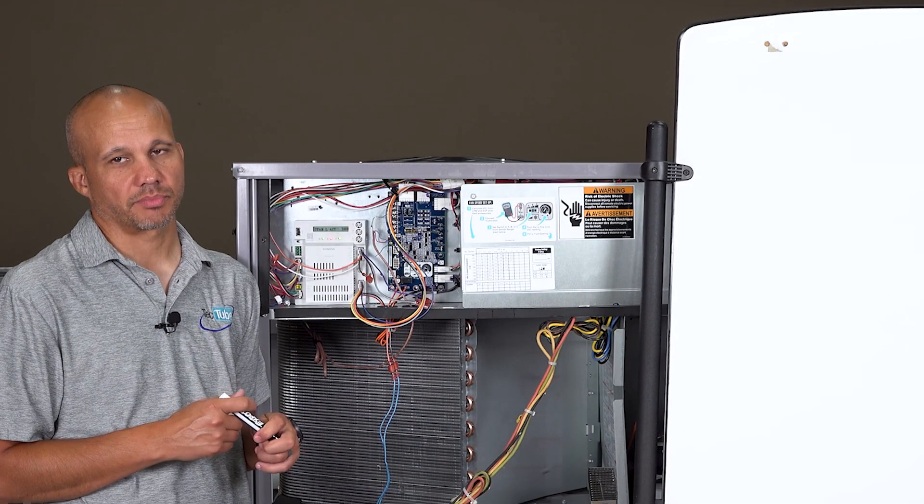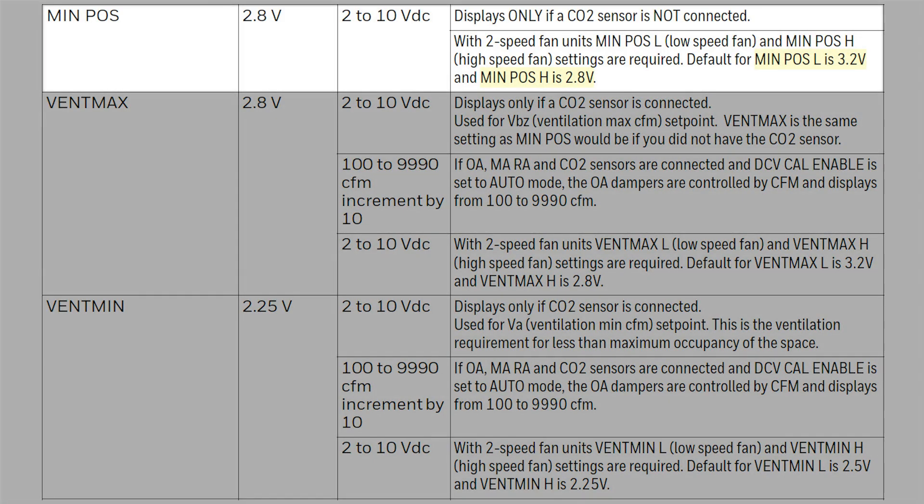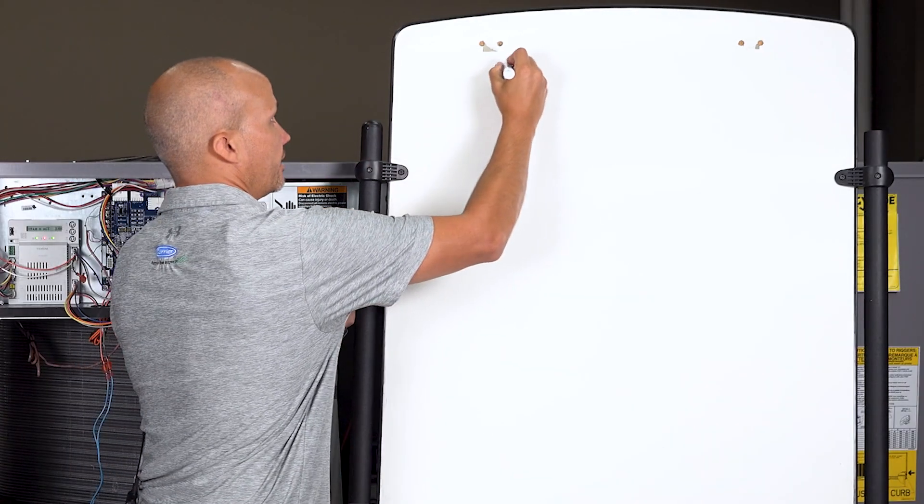I want to finish up something on the basic setup screens that is a little more confusing and more advanced. We have the fan low actuator position for minimum ventilation and the fan high actuator position for minimum ventilation. The hard part is that all of these minimum positions are not in CFM and they're not in percent damper open - they are in voltage, and that confuses a lot of folks. Right now I'm showing you fan low actuator position 3.6 volts and the high one is 2.8 volts.